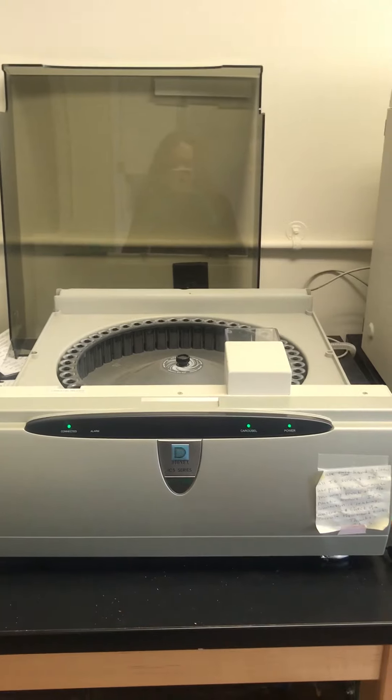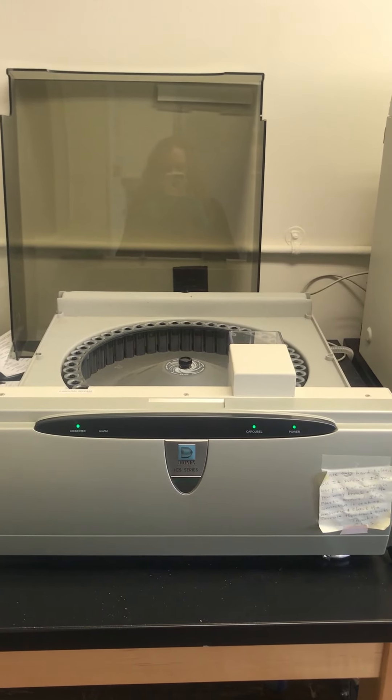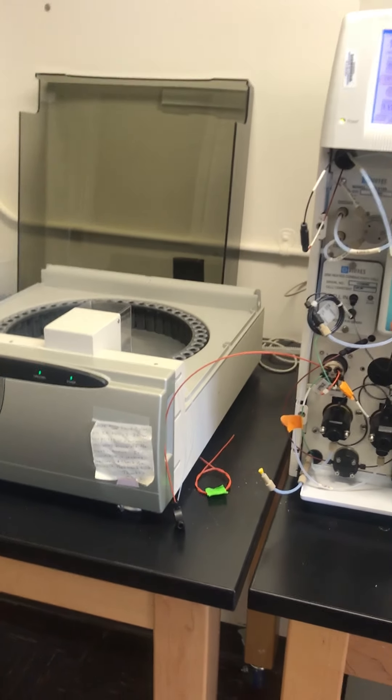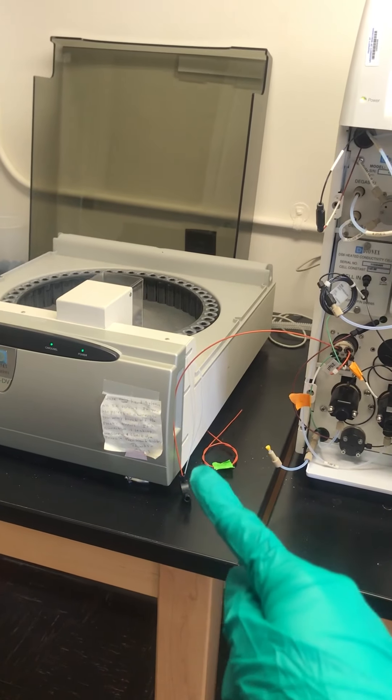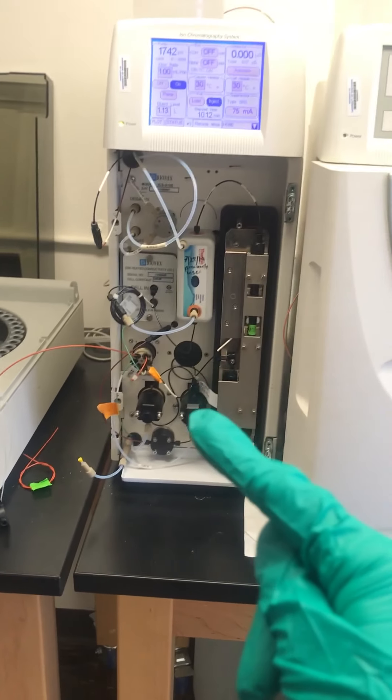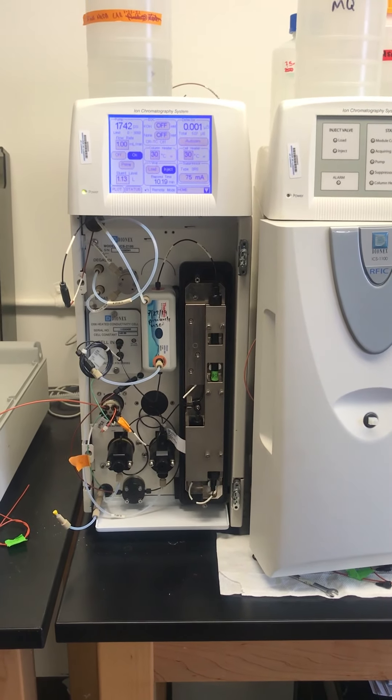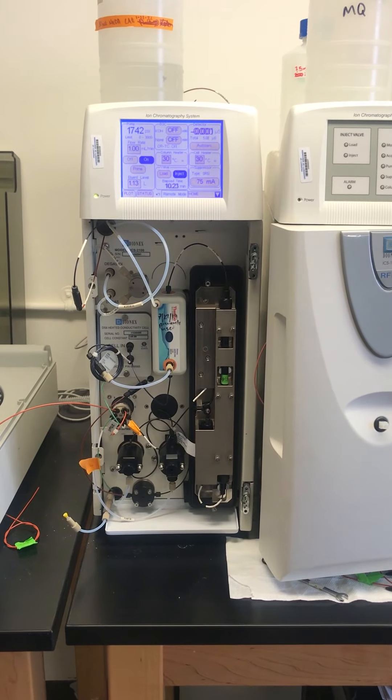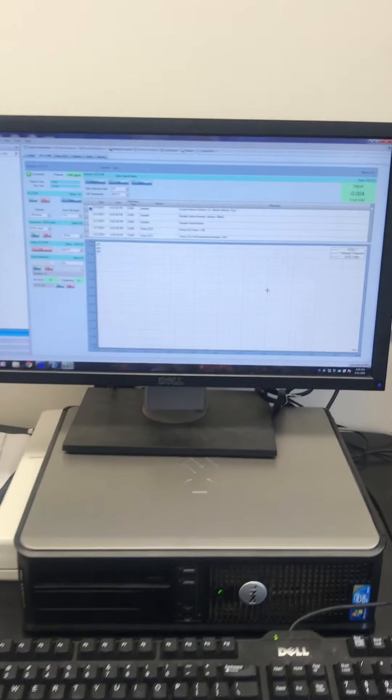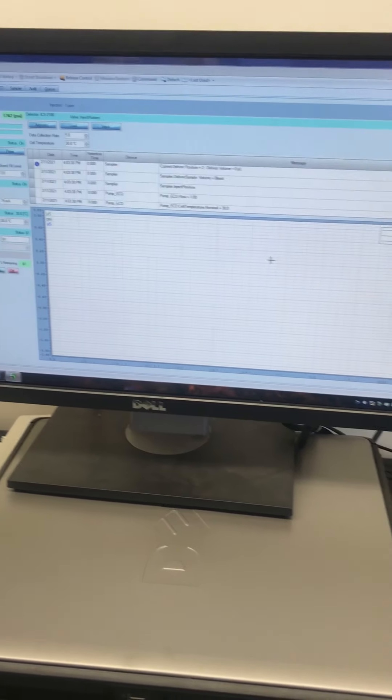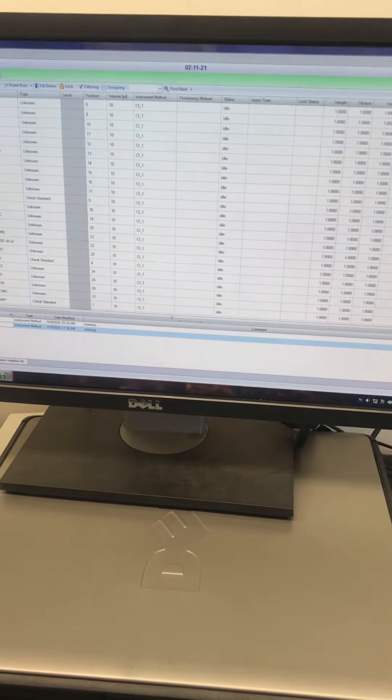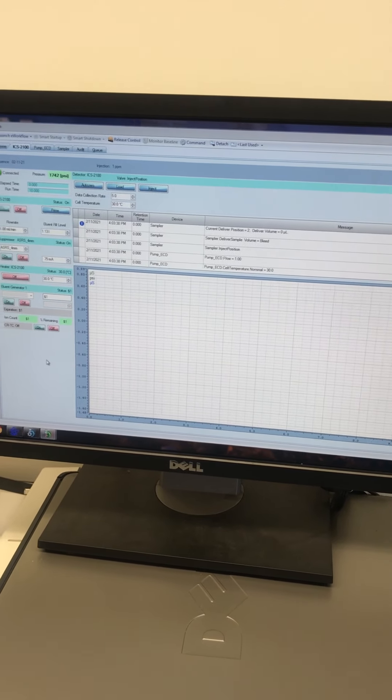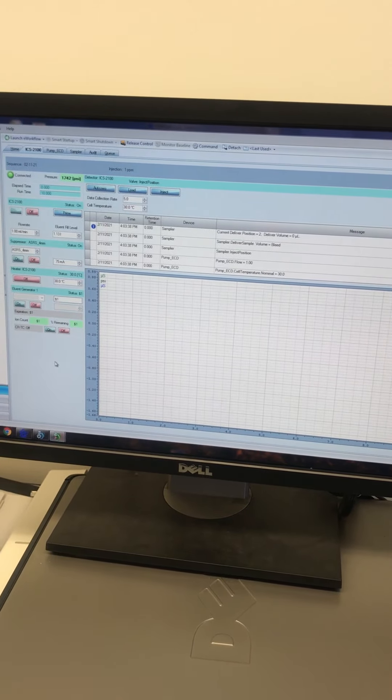This carousel is where the vials will be loaded for auto sampling. You can see the orange tubing that's connected here brings the sample into this part of the machine, and this is where the magic happens, where it detects the chloride concentration. Controlling everything over here is a computer where I load information about all the samples, and this is where the output comes so I can see the numbers.